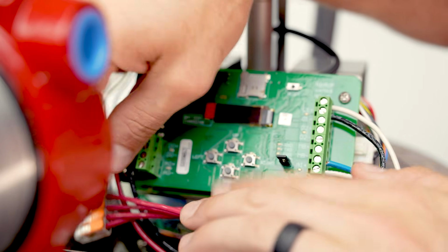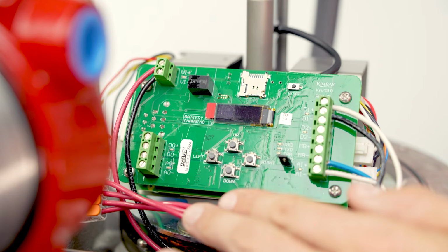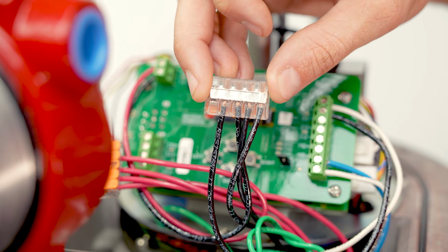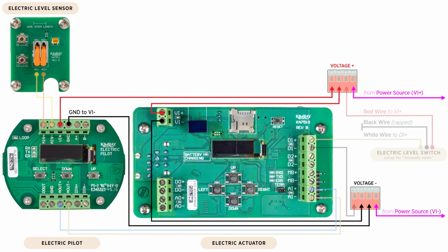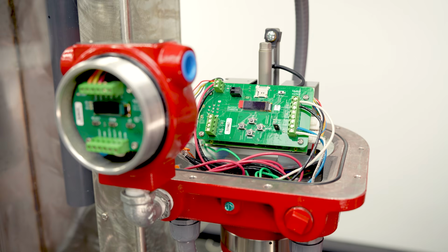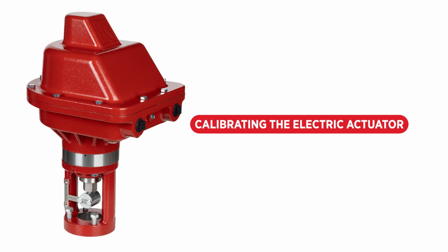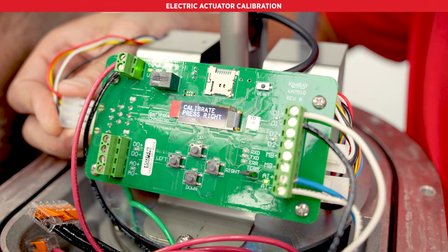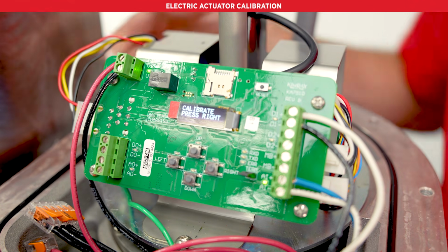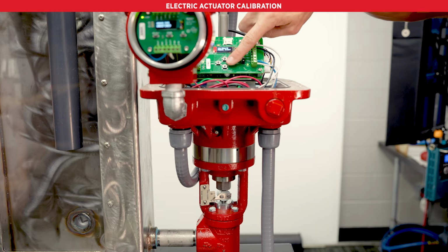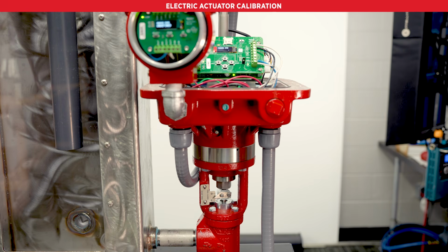Now we're going to connect the voltage into the actuator board. These power wires are connected to the loop. Voltage in positive and negative coming from the power source are connected in that loop to all other devices. With wiring complete, you can now turn on your power. Now it's time to calibrate these components. Plug in your backup battery on the electric actuator. To calibrate, simply press right and it will calibrate itself in about 20 seconds.